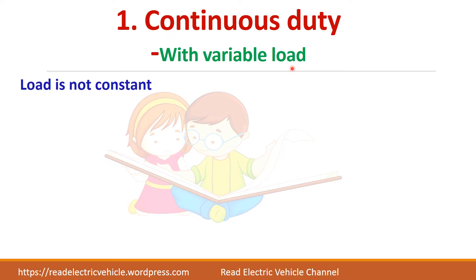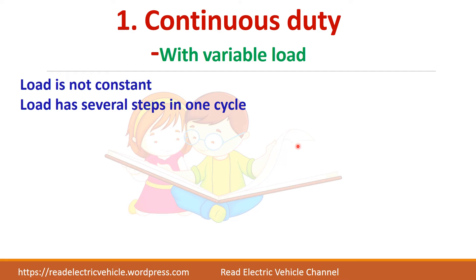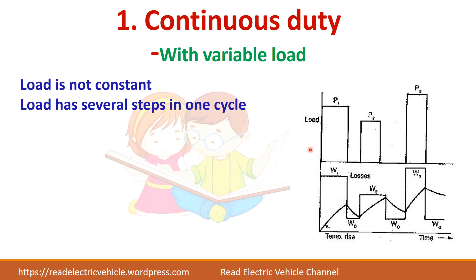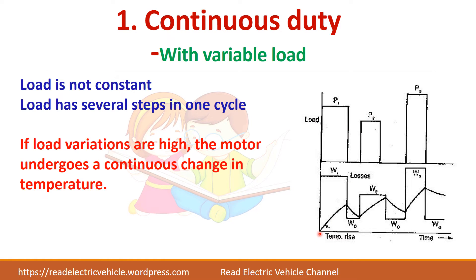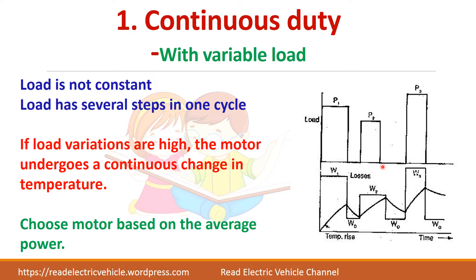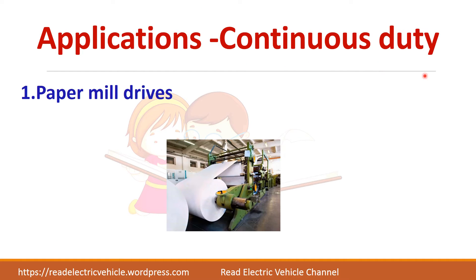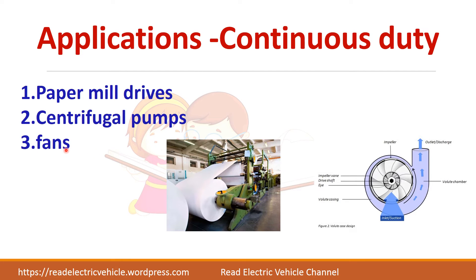Next is continuous duty with variable load. Here, the load is not constant but it varies in steps. For example, like a juice maker — you add some fruits, then after some time you add more. So your load is variable but the machine is on continuously. The temperature will rise for some time, then decrease, then rise again. In this case, choosing a motor is difficult because we don't know the particular load value, so we have to choose the motor based on the average power. Applications of continuous duty include paper mill drives, centrifugal pumps, and fans.